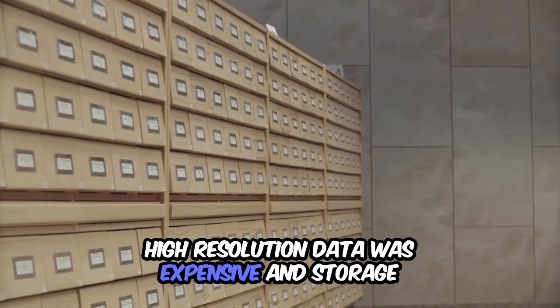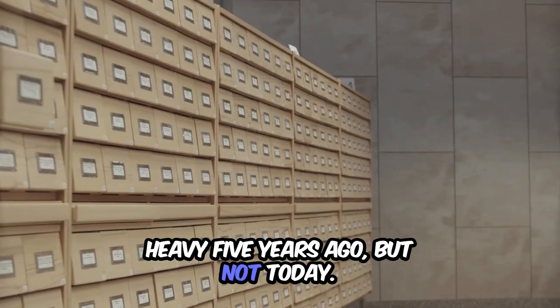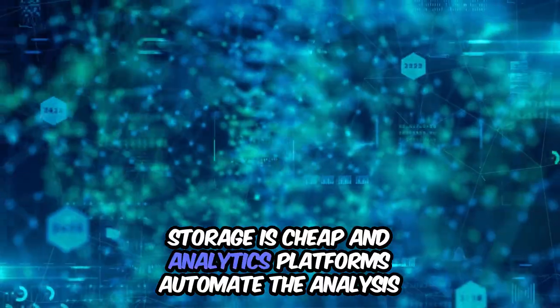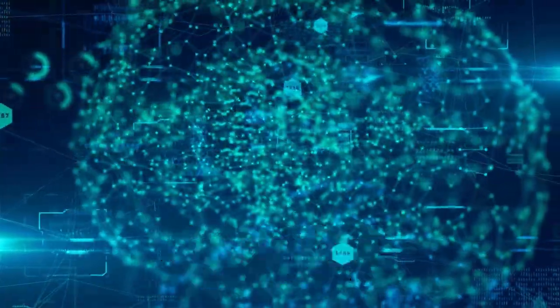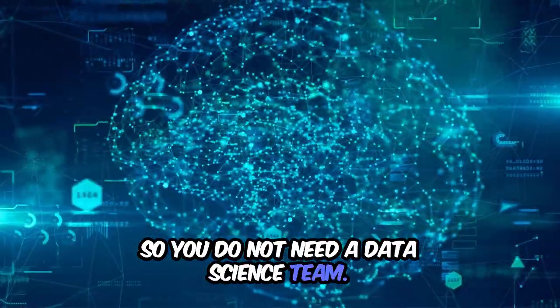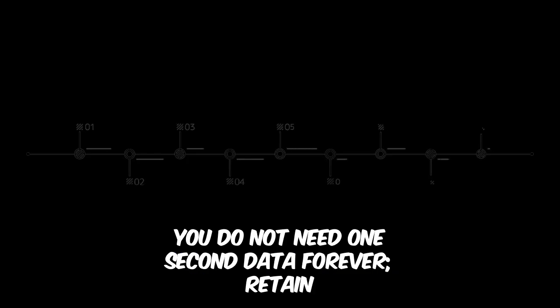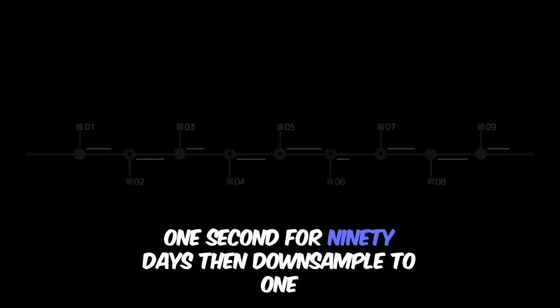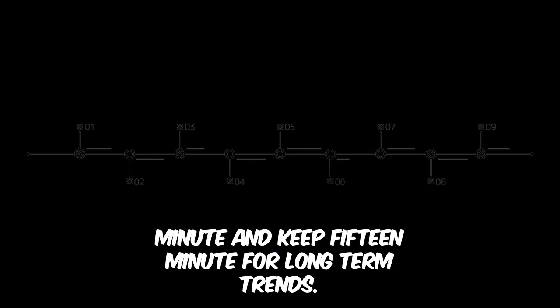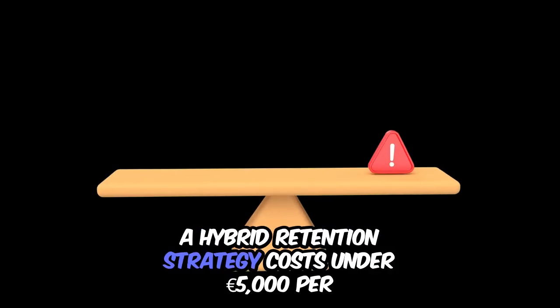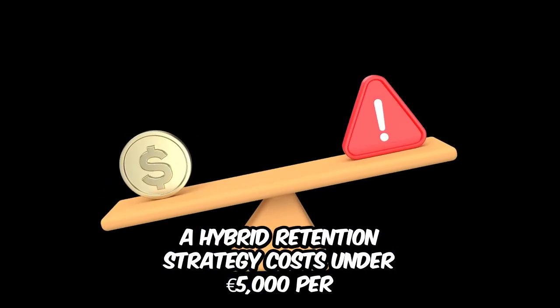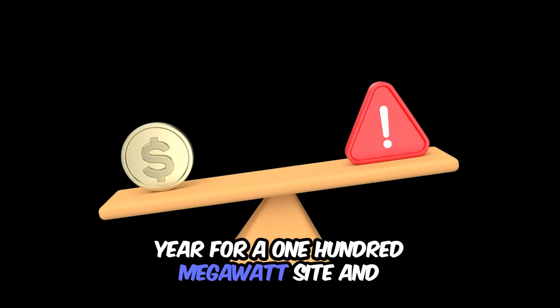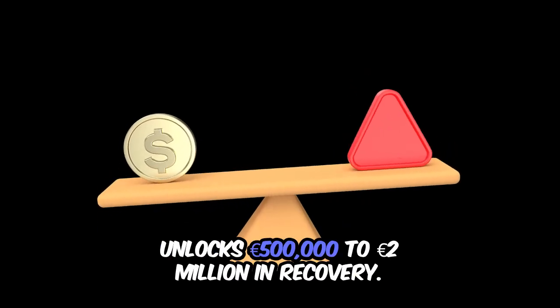High-resolution data was expensive and storage-heavy 5 years ago, but not today. Storage is cheap, and analytics platforms automate the analysis, so you do not need a data science team. You do not need 1-second data forever. Retain 1 second for 90 days, then downsample to 1 minute, and keep 15-minute for long-term trends.